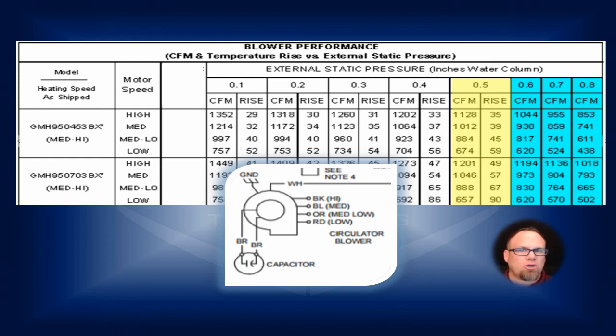Now you go to medium low, chances are between medium and medium low, you probably won't drop to another static level. So it'll probably stay right in that same guideline there. So you probably drop down to maybe around 741 in this instance. And then once you drop down to the low speed, you're going to be at that 620 CFM range. And those are examples. Those are not standard by any means. You know, there is no such thing as standard. Every install is different. Every piece of ductwork in every home is a little bit different.